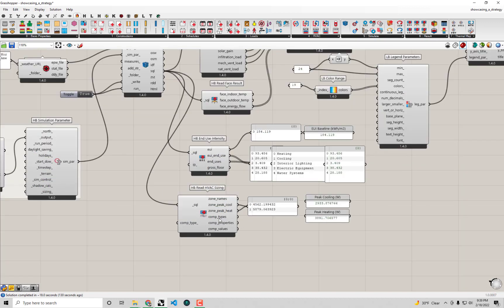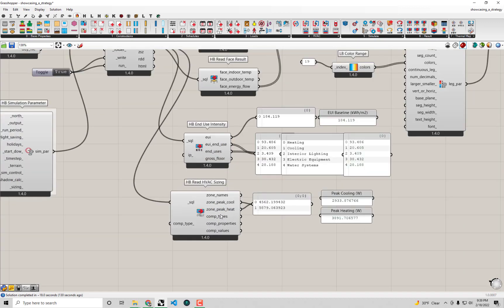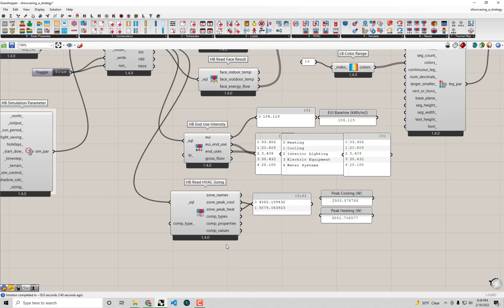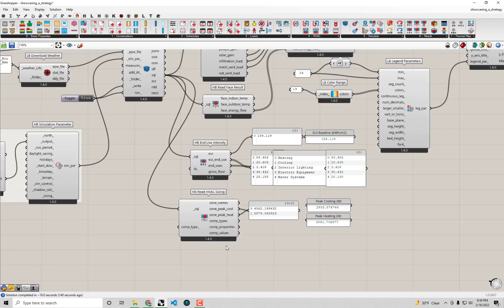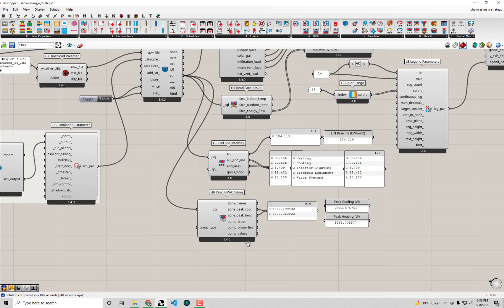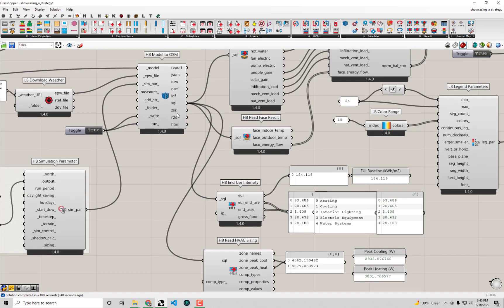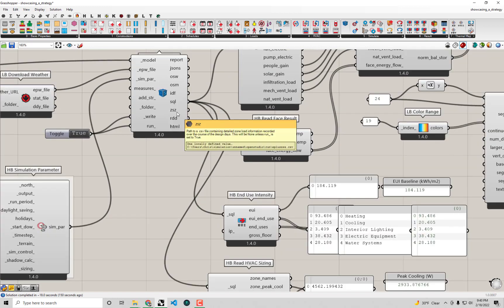You can see there are other outputs of this component that will give you sizes for different components of the HVAC system. But the key thing I want to understand right now is actually not in the SQL result file at all, but in this other CSV file, this ZSZ CSV file that EnergyPlus outputs. This keeps a record of that sizing calculation that runs at the very start of the simulation.